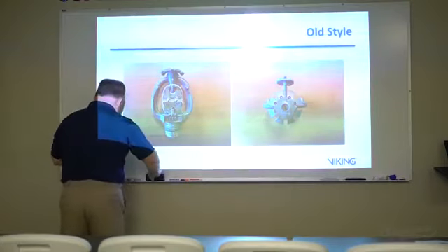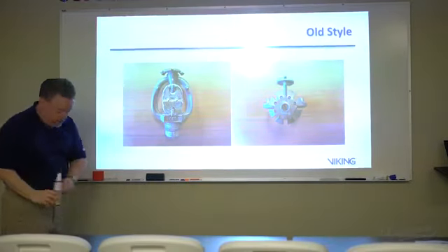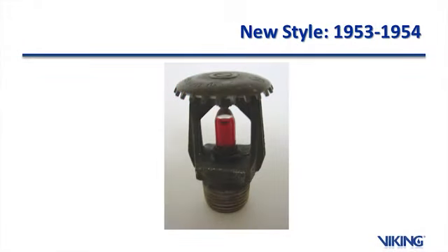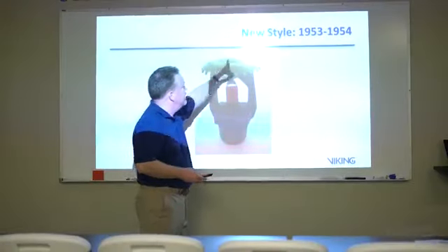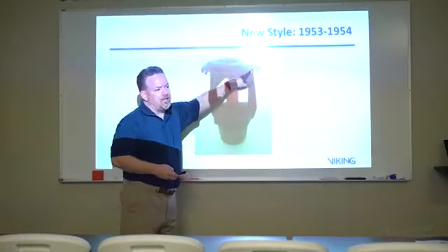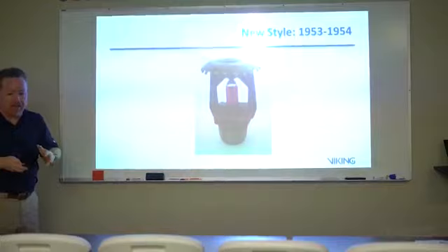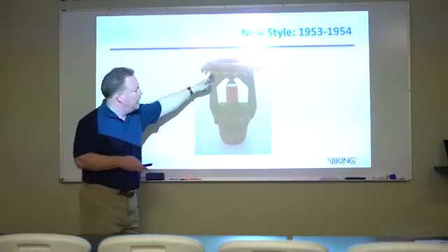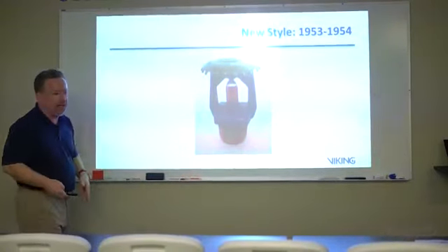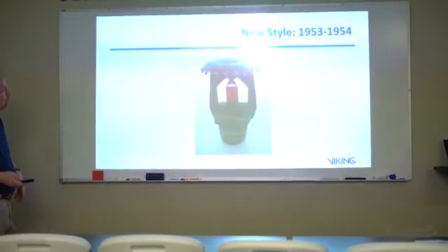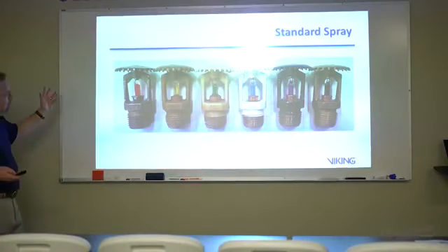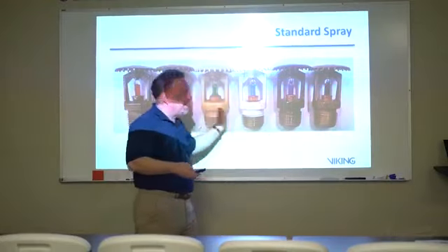Then we developed a new style, 1953, 54-ish. And you can see the big change here. The big change was the deflector size. Now we were capturing almost 100% of the water that was coming out. We were capturing it and redirecting it down.